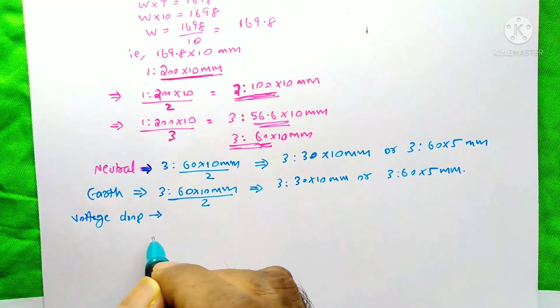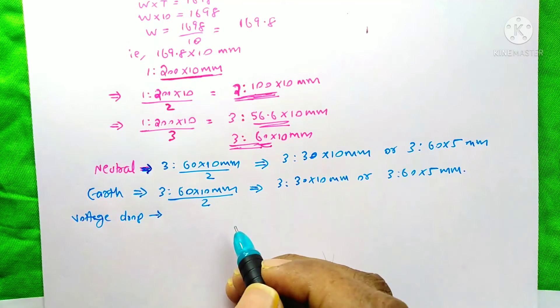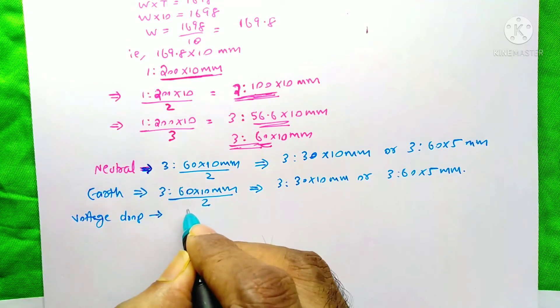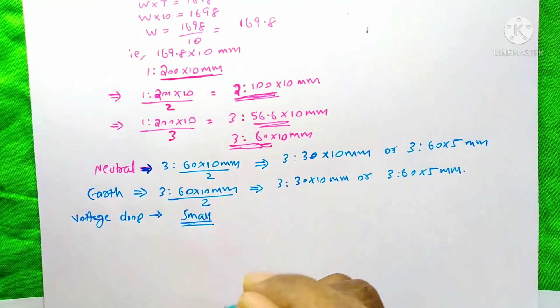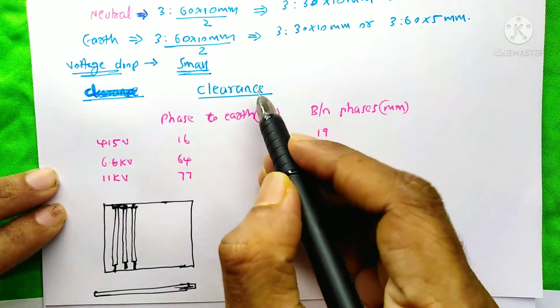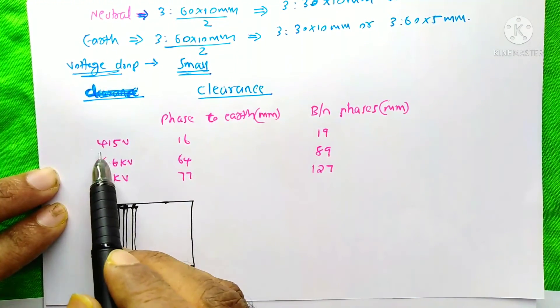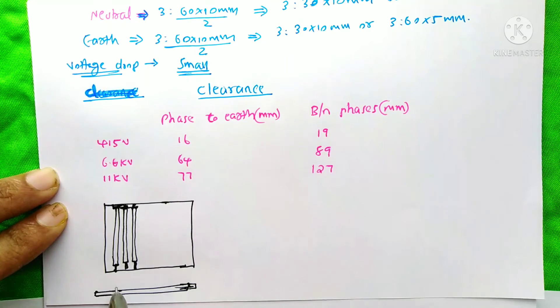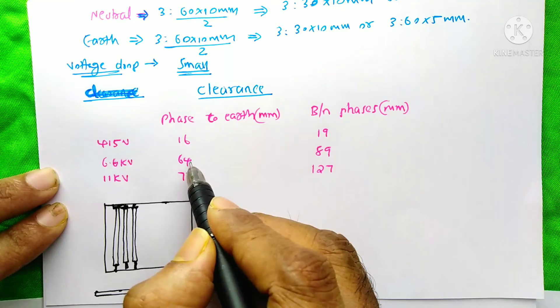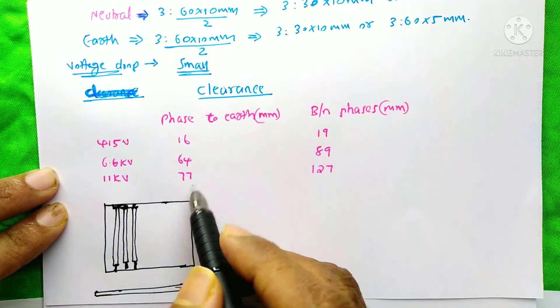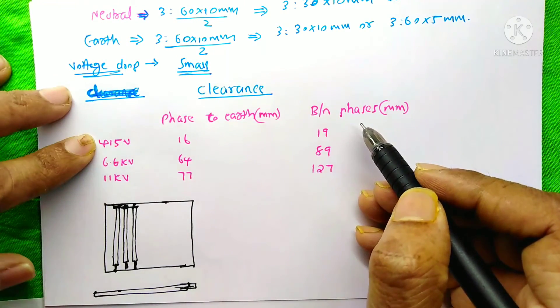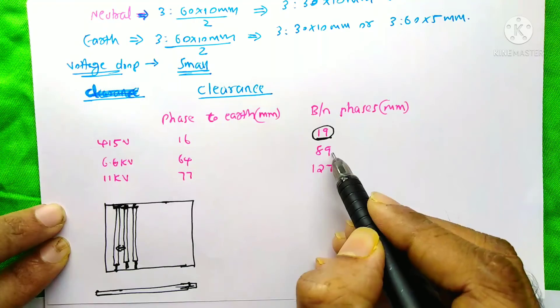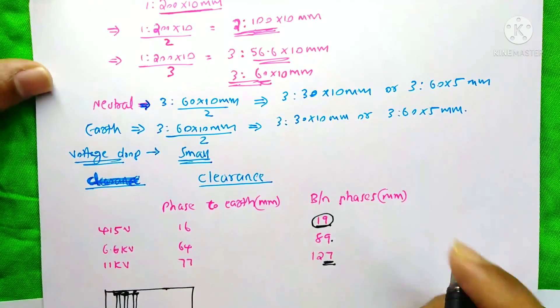For cable runs there is a chance of voltage drop due to length, but bus bars are compact inside the LV room so voltage drop is not a concern. Regarding bus bar clearances: at 415 V, phase-to-earth clearance = 16 mm; at 6.6 kV = 64 mm; at 11 kV = 77 mm. Between phases: at 415 V = 19 mm; at 6.6 kV = 89 mm; at 11 kV = 127 mm.